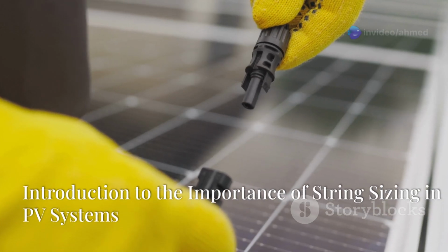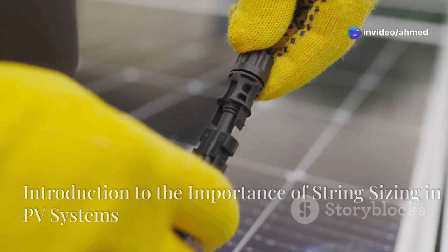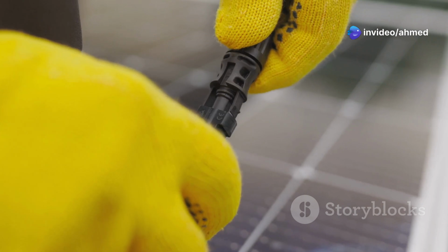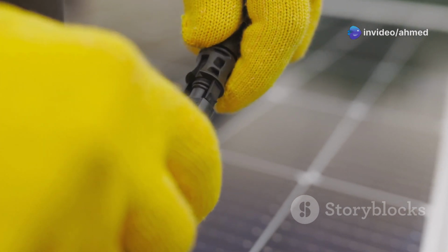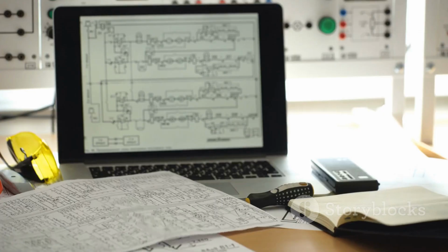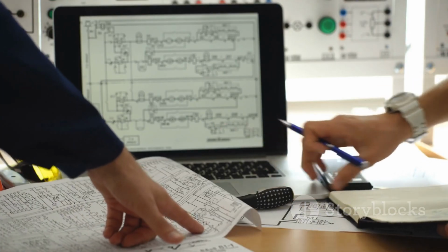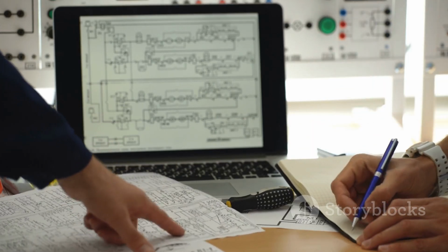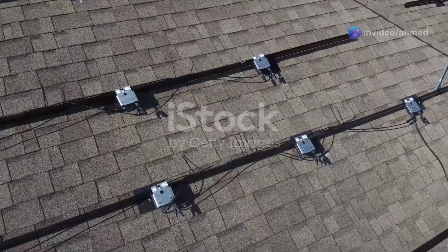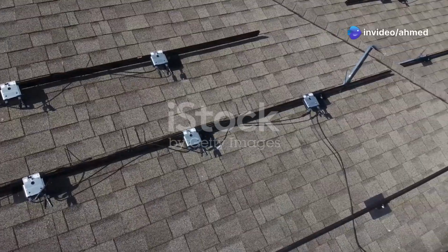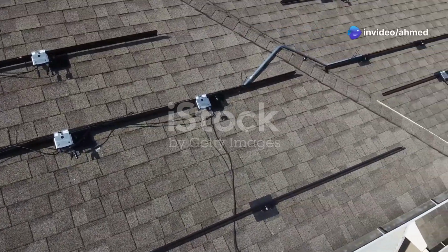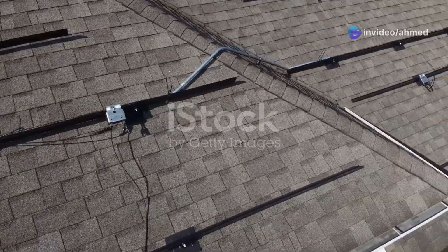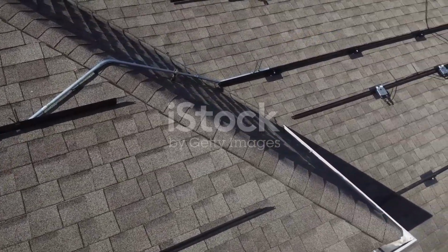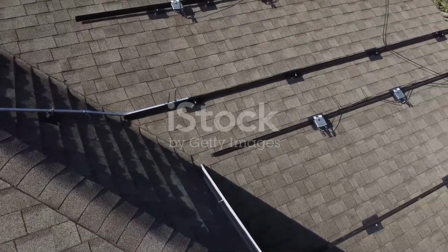When designing a solar PV system, knowing the minimum and maximum numbers of PV modules to connect in series as a string is critical. System designers regularly performed this calculation before the advent of DC optimizers. Optimizers, module-level power electronics that dynamically manipulate the output voltage of modules, made this calculation much less common, especially in roof-mounted arrays that require rapid shutdown.